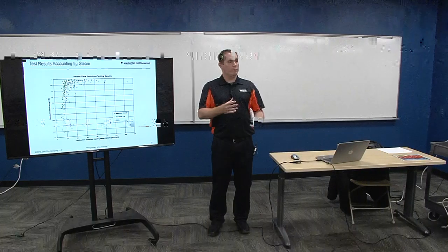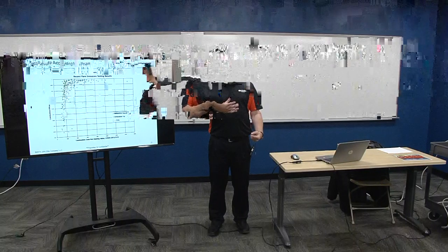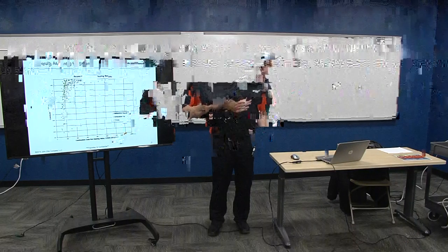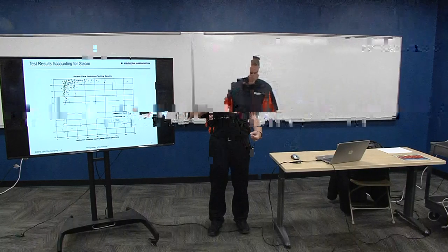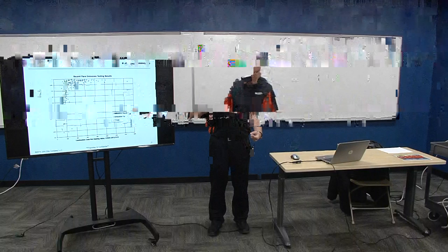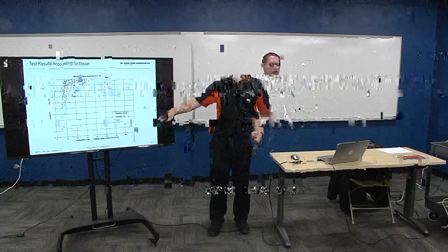It's not necessarily by the gas coming to it, but it's the mixture above the flare. So that's where this combustion zone net heating value came in. It's now, what's the net heating value of the combustion zone, the area above the flare? So with this new principle, they kind of created this chart, and the EPA was going to start to use this data to rewrite or recreate the rules.